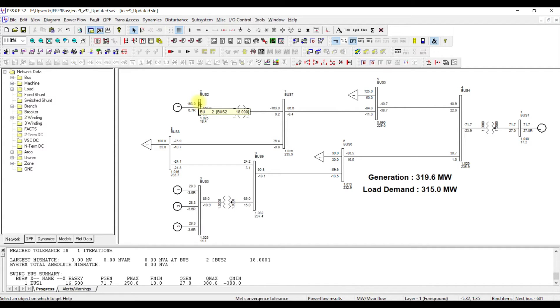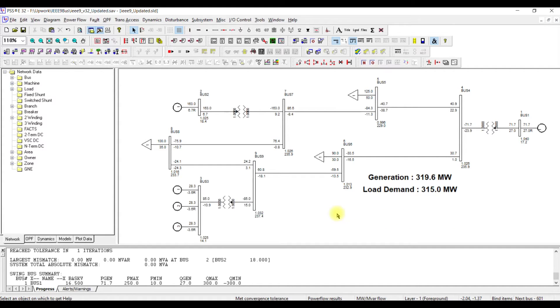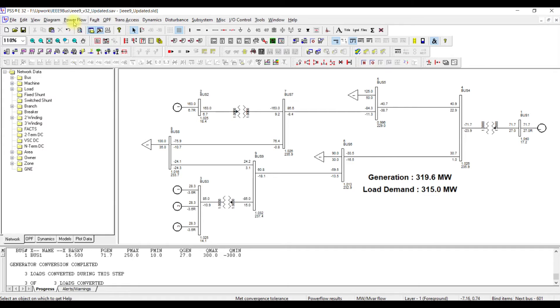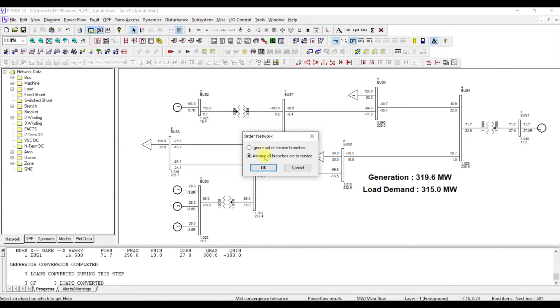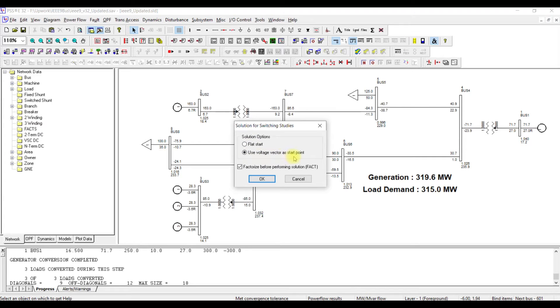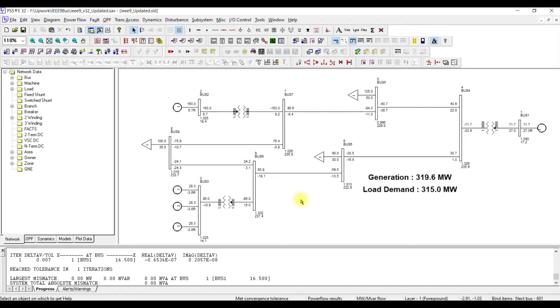To use this case for transient stability analysis, we first convert it. Go to Power Flow, then Convert — convert for generator, convert for load, all buses, convert, then Power Flow, then Solution, then Order, then Power Flow, then Solution, then TYSL, then use voltage vector as start point, then Factorize. The conversion is done. I will not save this converted file since I already have one — this was just to remind you of the conversion steps.